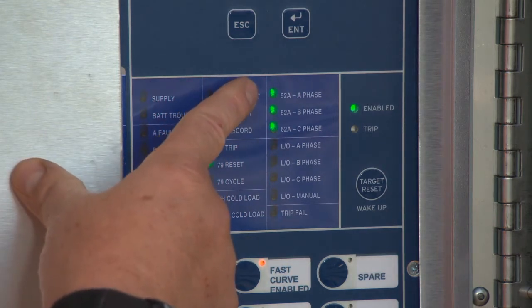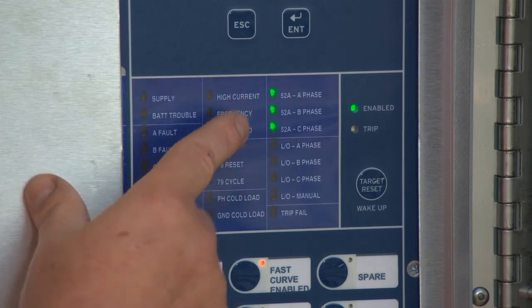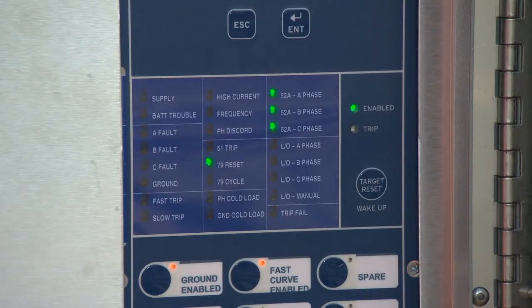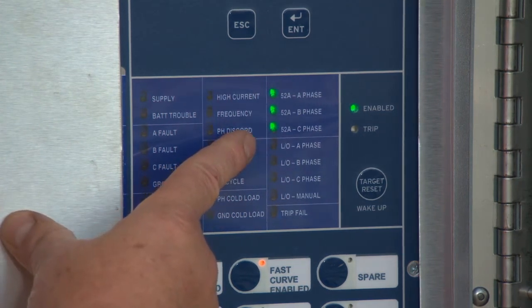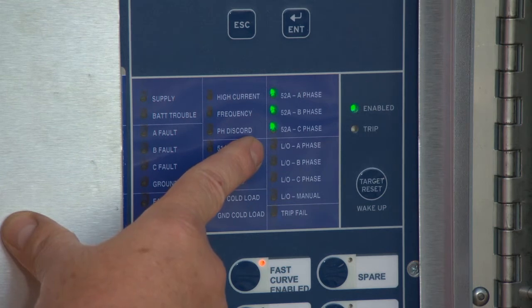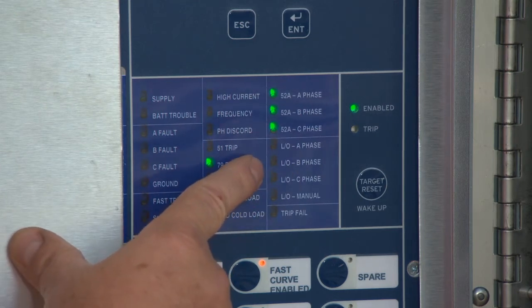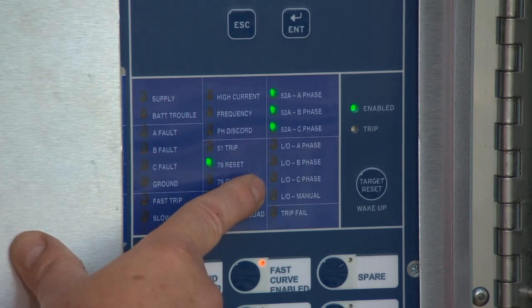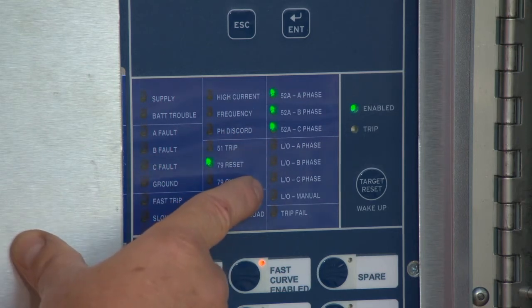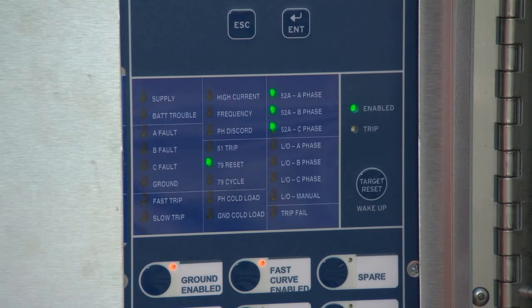Along the right side are the 52A A phase, 52A B phase, and 52A C phase indicator LEDs. These will be illuminated green when the recloser is in the normally closed state. Next are the lockout indicator status LEDs. LO A phase will turn red, indicating a lockout state in the A phase. LO B phase will turn red, indicating a lockout in the B phase. LO C phase will turn red, indicating a lockout in the C phase. Any combination of these may be illuminated for a fault condition. These will be activated by the type of fault downstream. For example, a phase-to-phase fault would illuminate 2 of the LEDs.